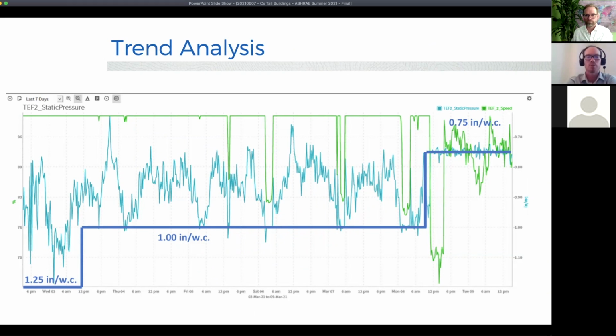Set points, of course, once we start doing some of that fine tuning, but it's also on the programming side, right? There's a lot of PID tuning. There's a lot of background programming that happens, and those adjustments need to happen through testing. Tall buildings need commissioning. And that's a great point, you need to be looking at the trends at a level where you can see if a valve is hunting, because things happen very dynamically in a building that is this tall. So you can have, like John mentioned, PID loops that are just way out of tune. You can see a valve fluctuating every second in some cases. So you want to be doing a lot of your commissioning through trend analysis and data analytics, which we'll touch on more in a minute.